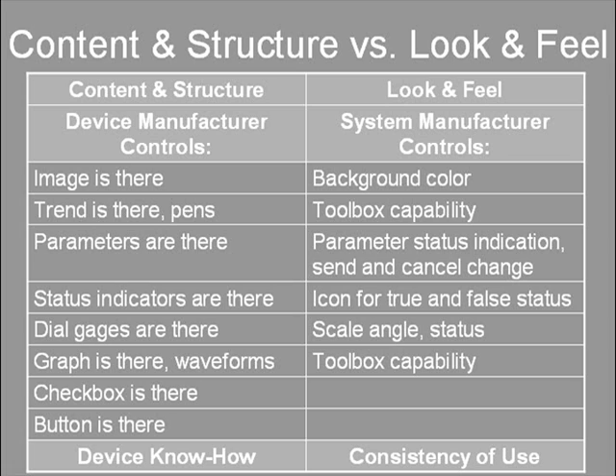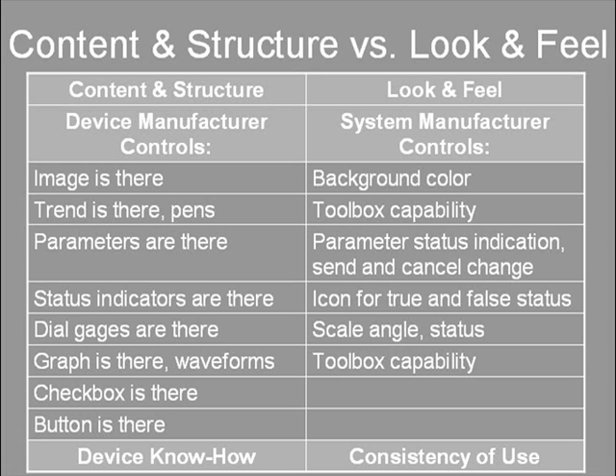It is the device manufacturer that controls if there is an image on the page or not. The system manufacturer controls if the background is white or grey. It is the device manufacturer that controls if there is a trend on the page and how many pens or values it is recording. The system manufacturer controls how its tool for pan and zoom works. It is the device manufacturer that controls which parameters are displayed on the page. The system manufacturer controls where to click to send a changed value to the device and how it is indicated the value has been changed and must be downloaded.